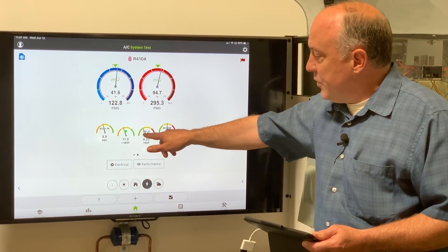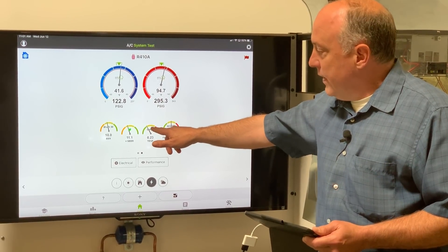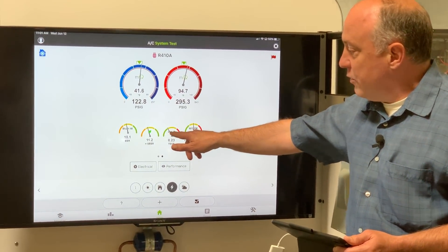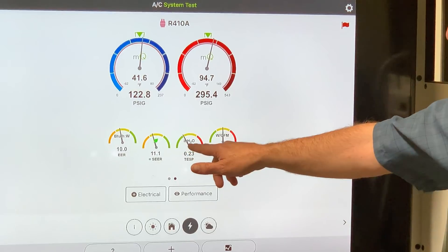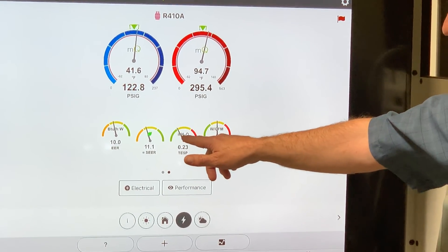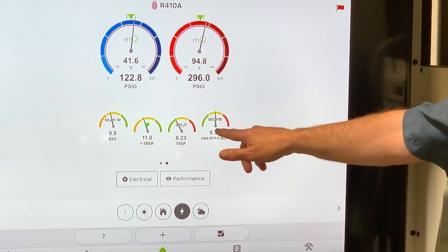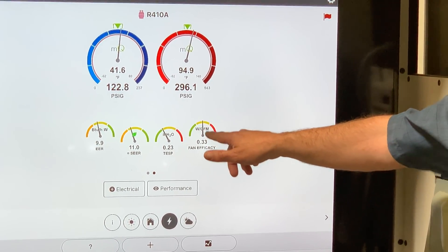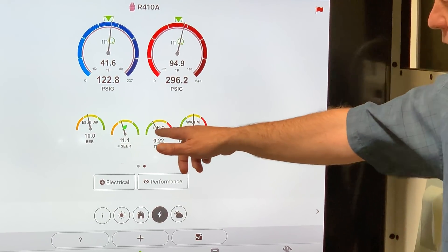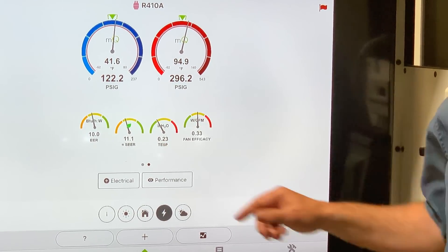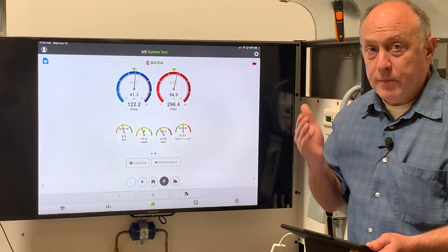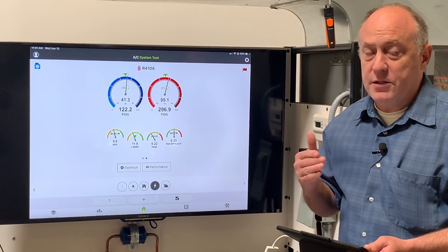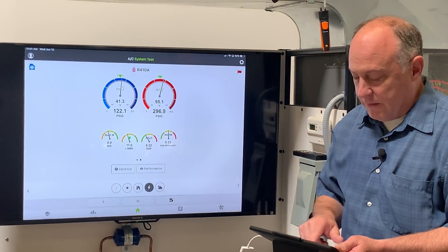Total external static pressure has a green, yellow, and red. We're in the yellow to green range, which means we're in a decent external static pressure range. Fan efficacy is at 0.33, which is also in a good range. Green is obviously better the farther into it we are, but that yellow band is totally okay for this type of stuff.